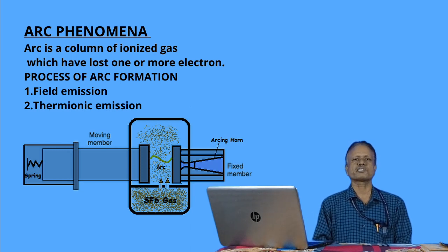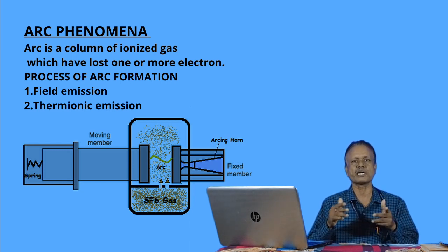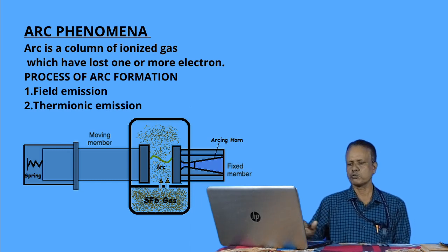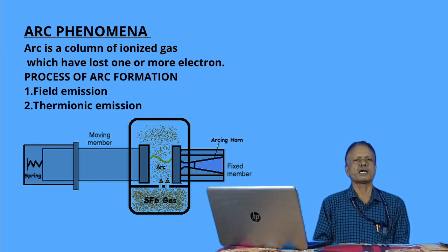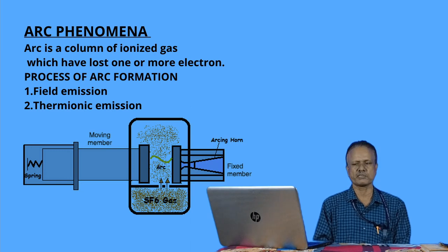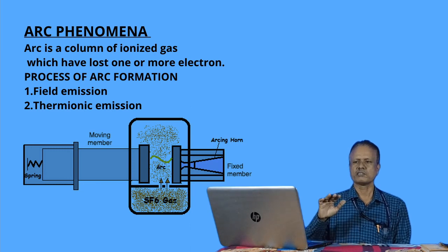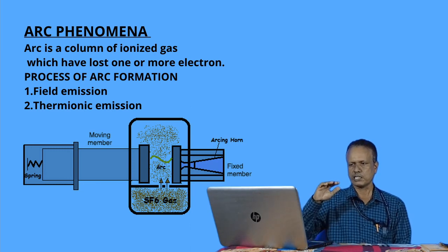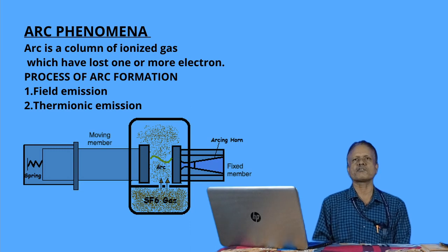Thereafter the process of arc formation. So if we go to the arc extinction process, so there are two methods. We'll first discuss the field emission method, then the thermionic emission method. So first of all, come to field emission.